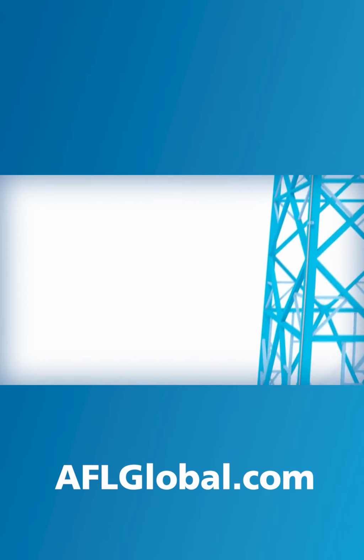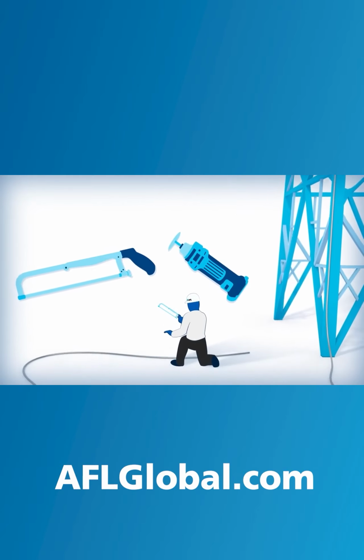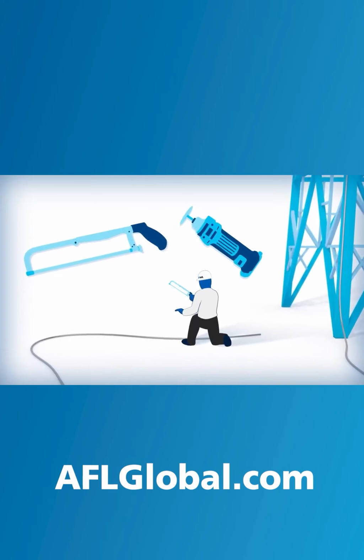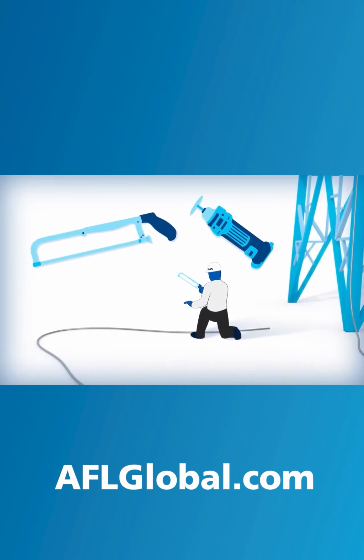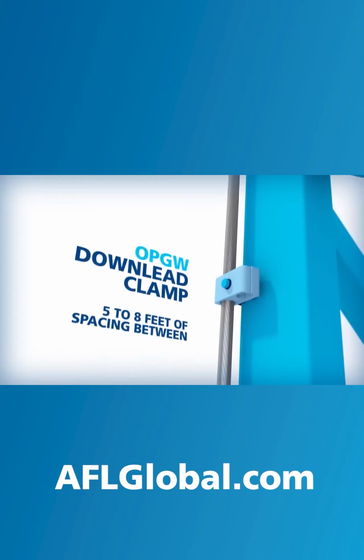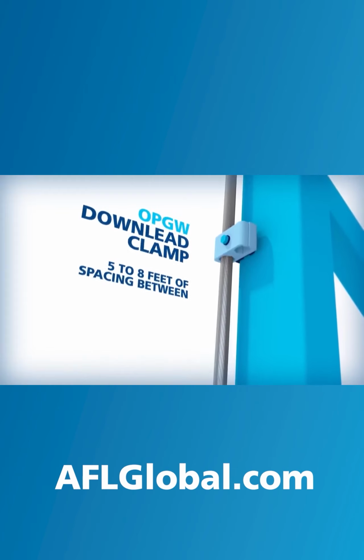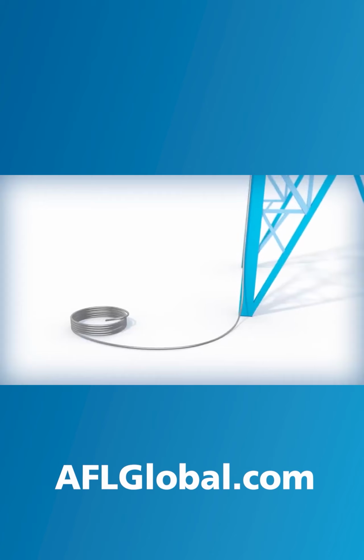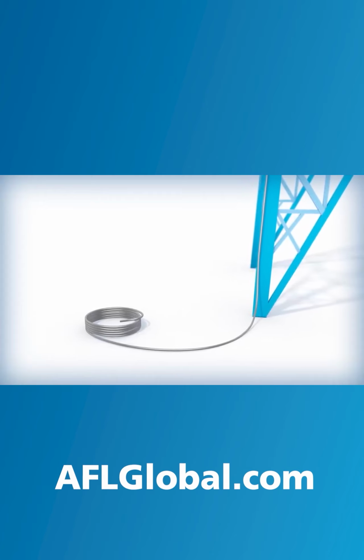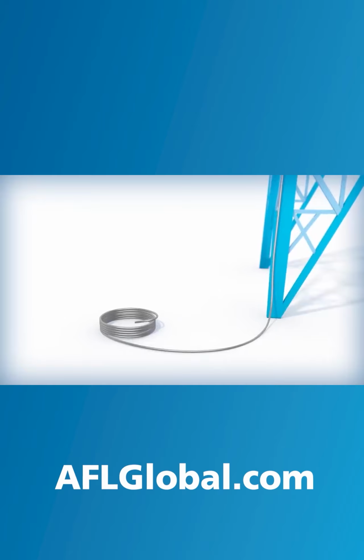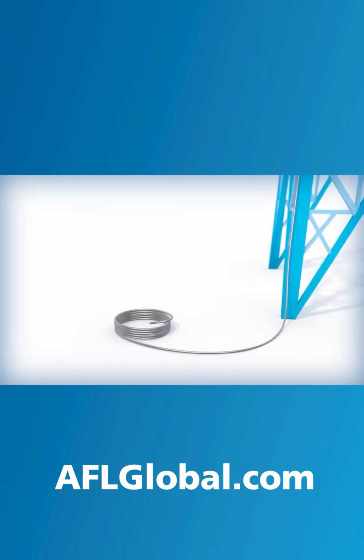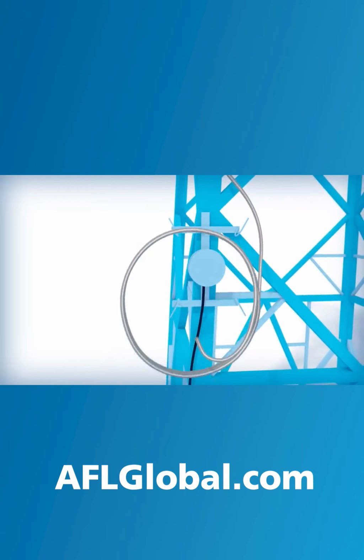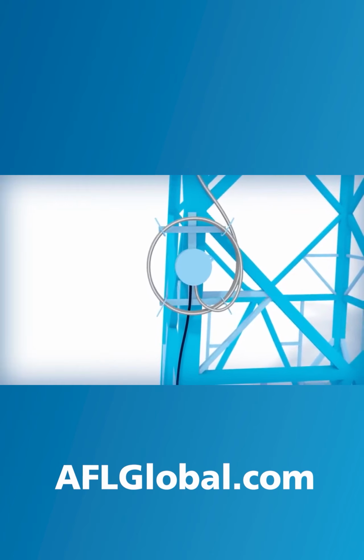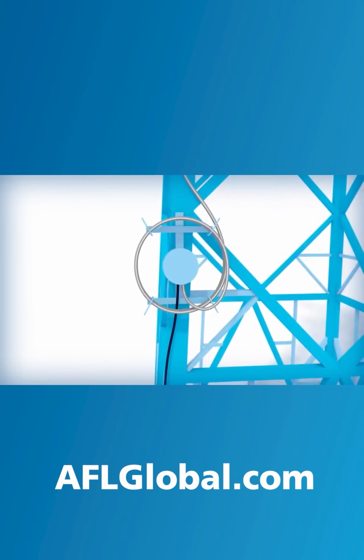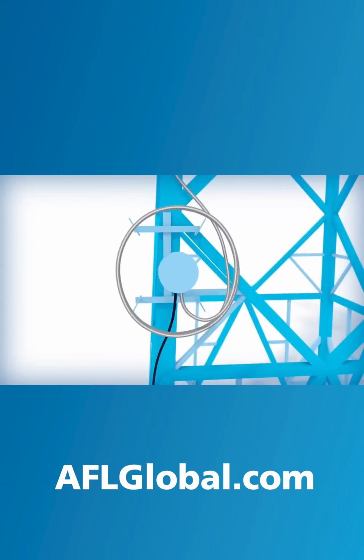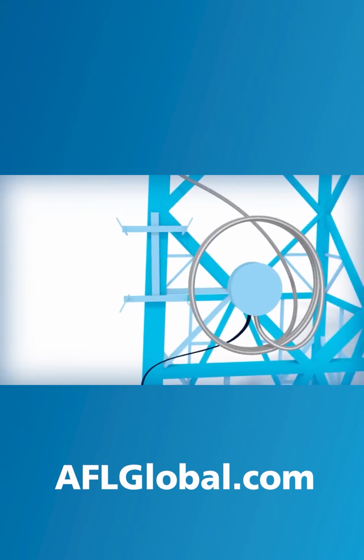When cutting the OPGW, a hacksaw-type cutter or rotary saw should be used to avoid crimping the cable and damaging the optical units. The OPGW is trained down the structure using downlead clamps. In order to provide enough cable for splicing, the OPGW should extend beyond the bottom of the structure and be looped in coils for storage. To prevent damage, the coil should be fixed on the structure at the splice enclosure location. For future splicing and/or maintenance, the splice enclosure may be removed from the structure and brought to ground.